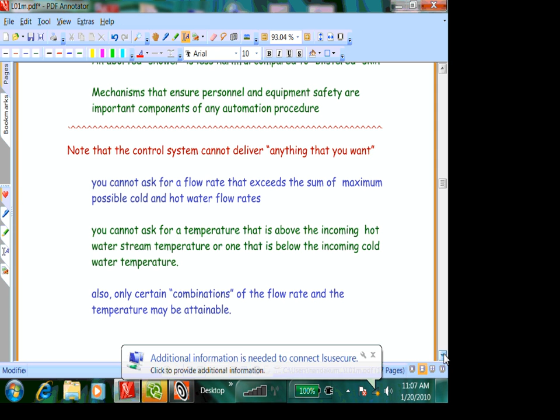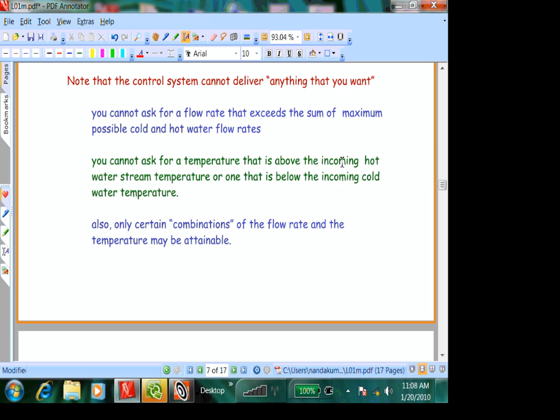So in this particular case, you cannot ask for a temperature that is above the incoming hot temperature or a temperature below the incoming cold water temperature. Those set the design limits. And if you need to address that issue, if there is an issue, then you need to go and redesign your cold water and hot water supply systems.